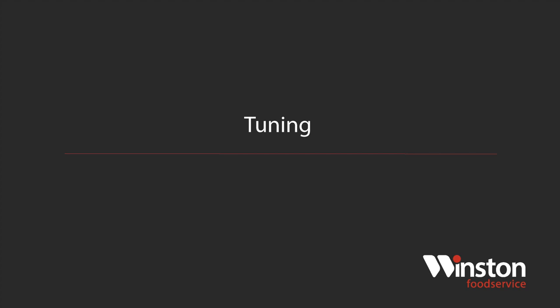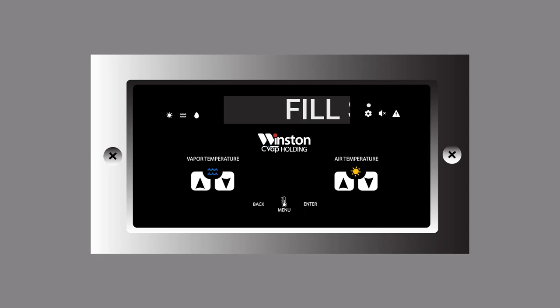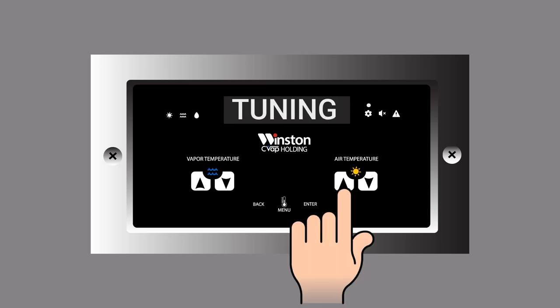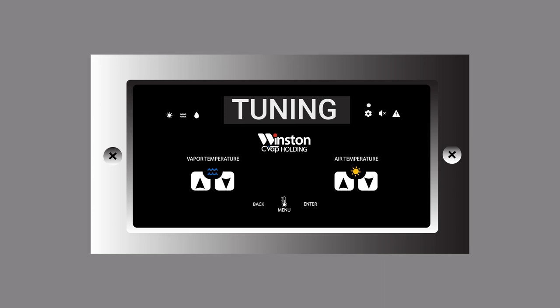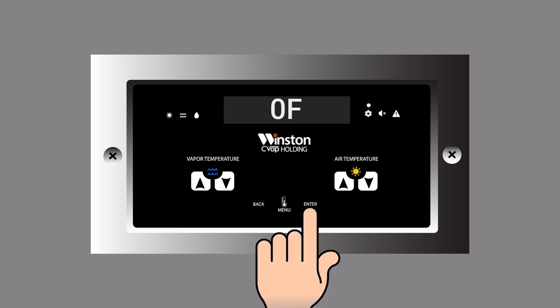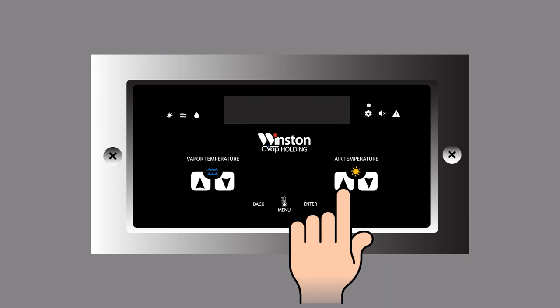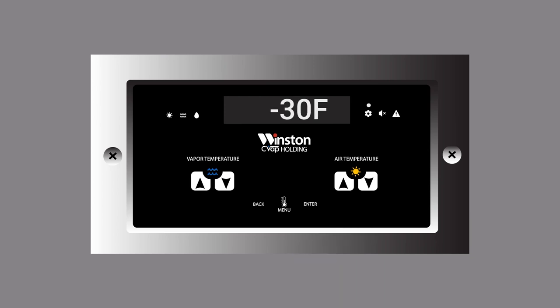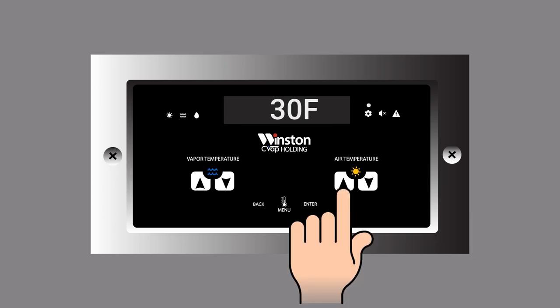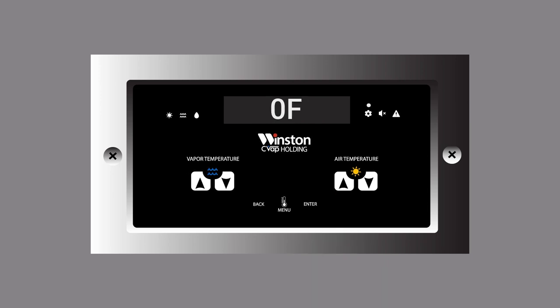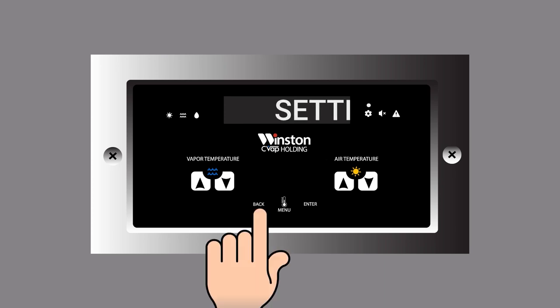Tuning. Tuning allows for vapor temperature calibration for the size of the unit. With fill system displayed, press the air temperature up button and tuning will be displayed. Select Enter. 0F should be displayed. Using the up or down buttons, tuning can be set anywhere from -30F to +30F. The default setting is 0F. Set your desired tuning. Select Enter. Tuning will be displayed. Select Back and settings will be displayed.